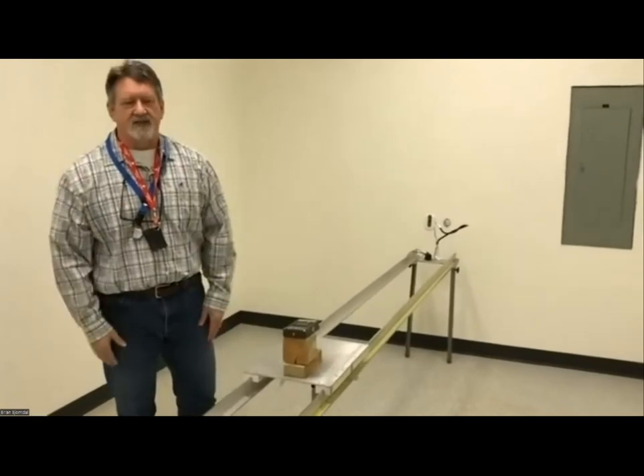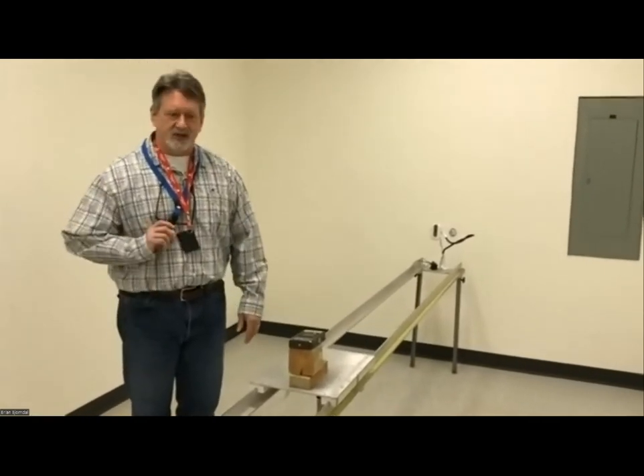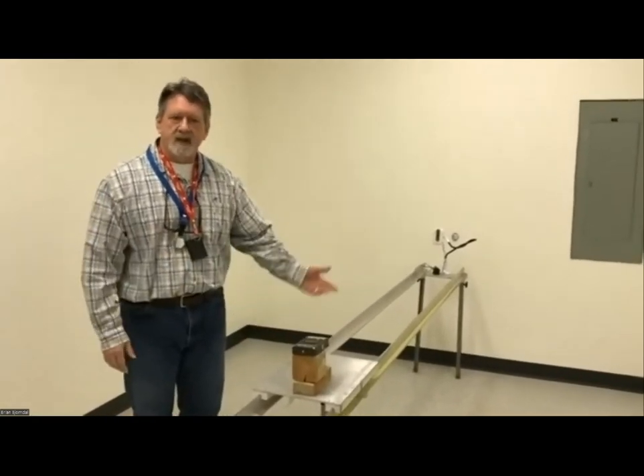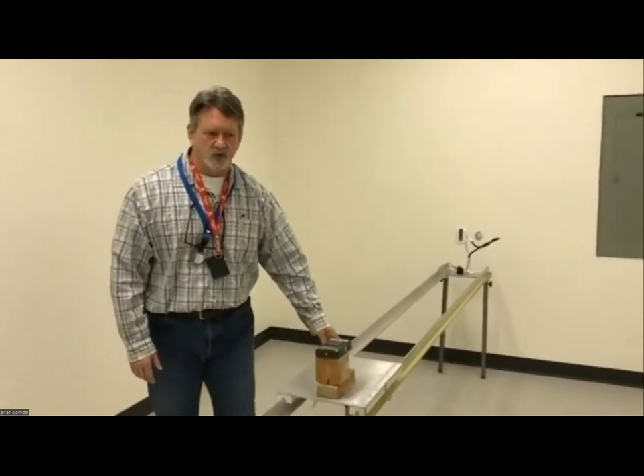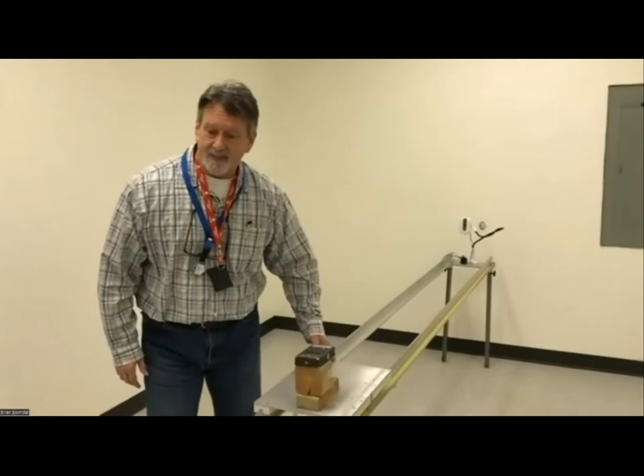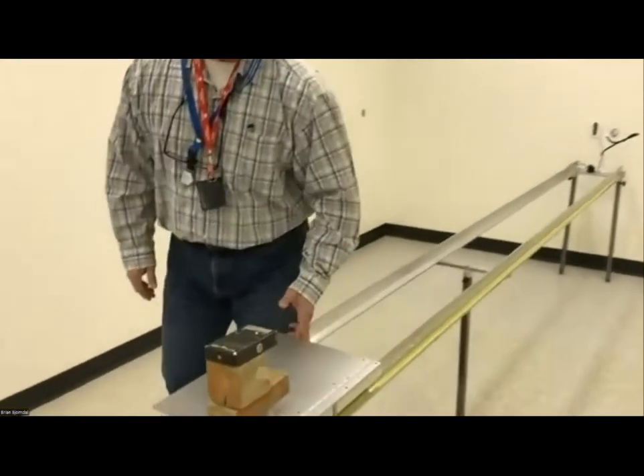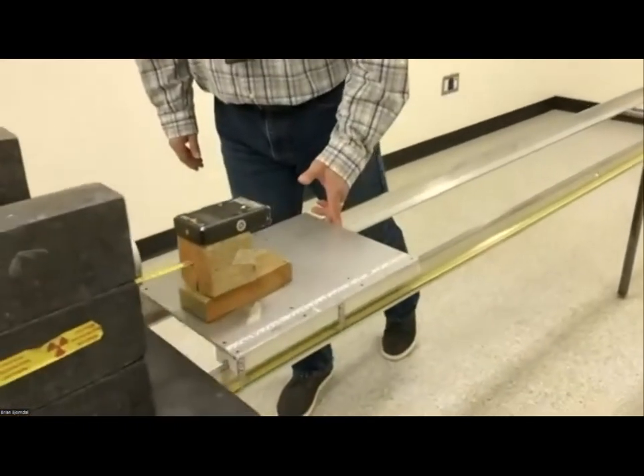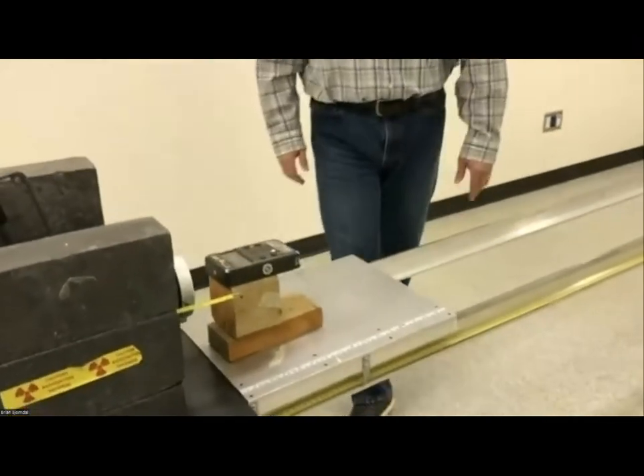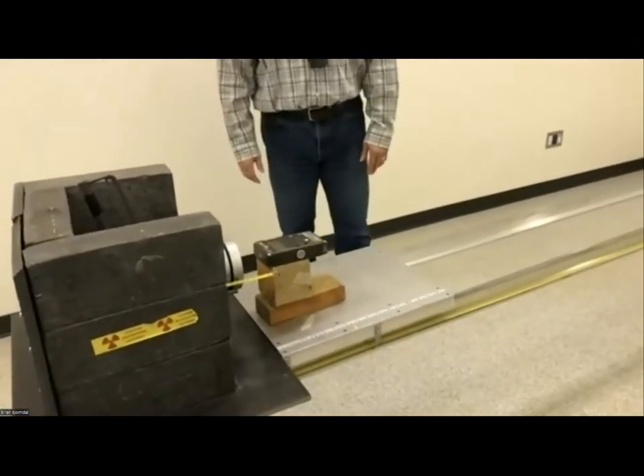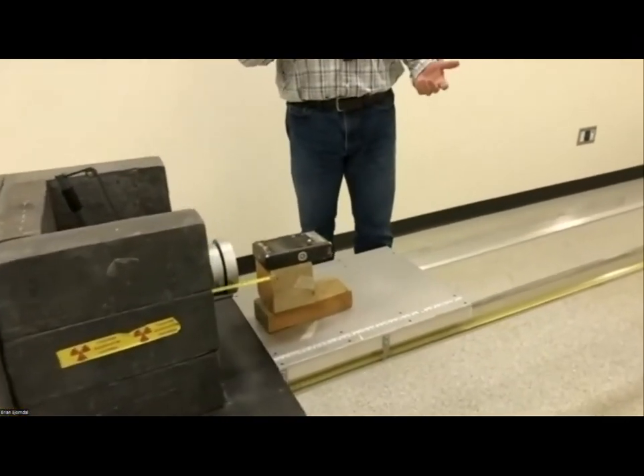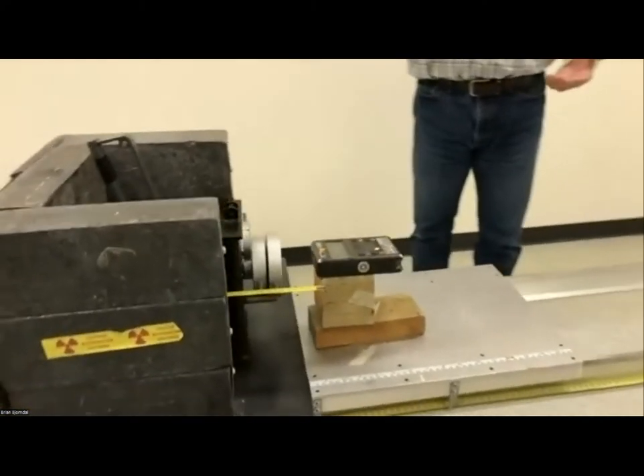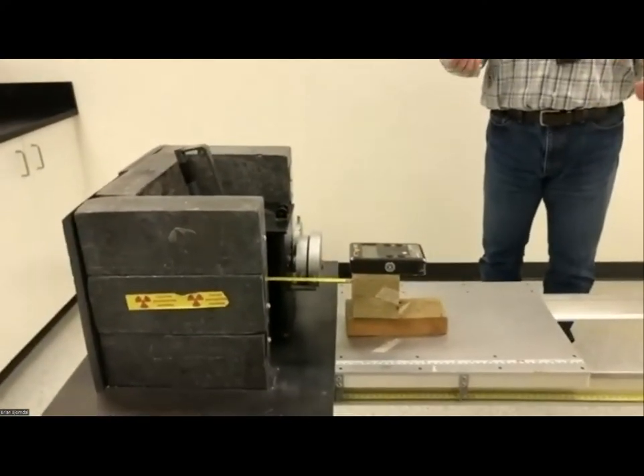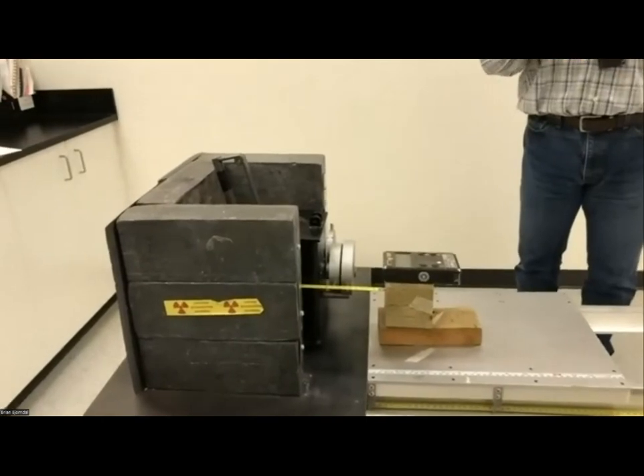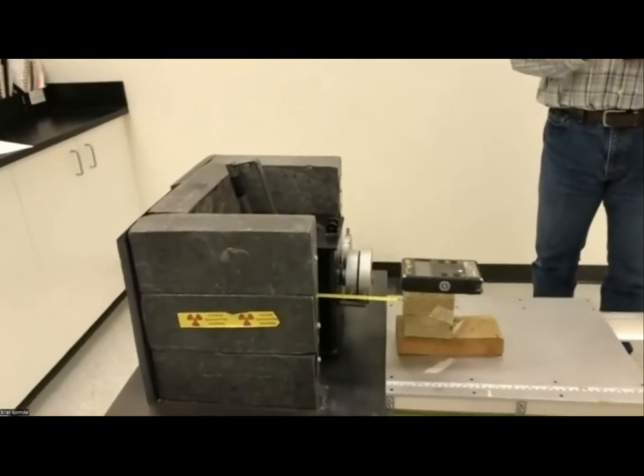So, I mean, they're widely available. And with an app on your phone or your iPad, you can set it up and read the instrument during the exposures. So this is what happens. If the instruments are exposed and we test the performance against our cesium-137 source, which is decay corrected to give us the right dose rate, and if it performs within plus or minus 20% and all the other things seem to be working properly, that's all logged on the data sheets.